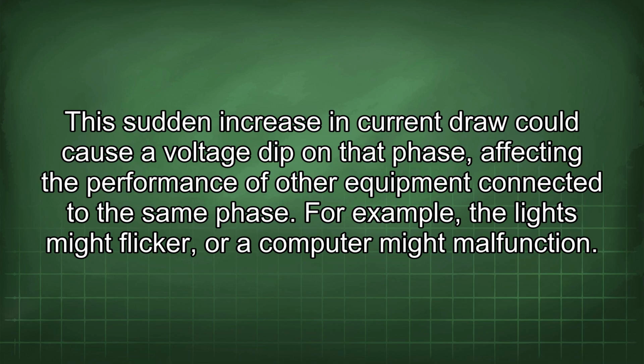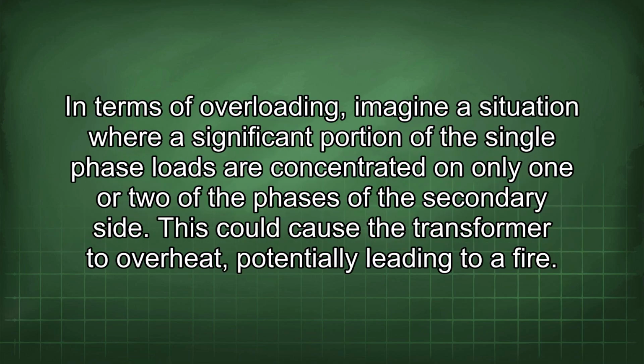For example, the lights might flicker, or a computer might malfunction. In terms of overloading, imagine a situation where a significant portion of the single-phase loads are concentrated on only one or two of the phases of the secondary side. This could cause the transformer to overheat, potentially leading to a fire.